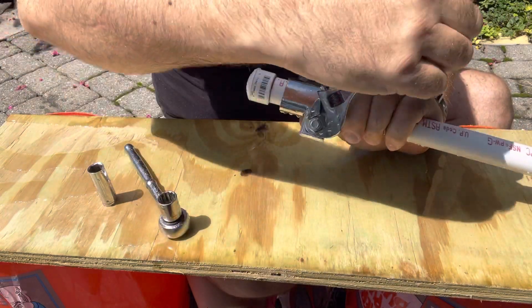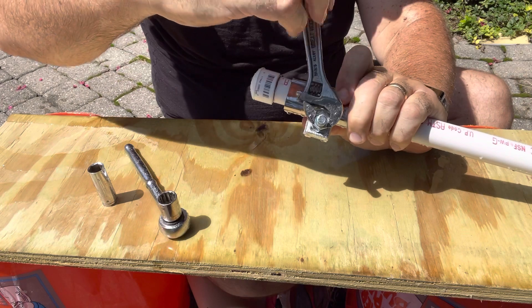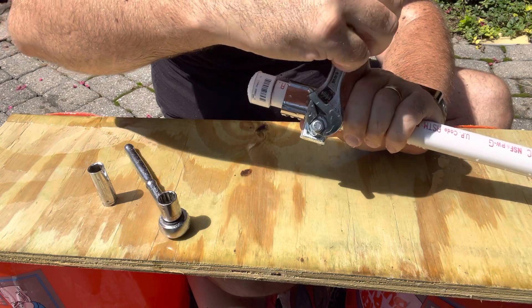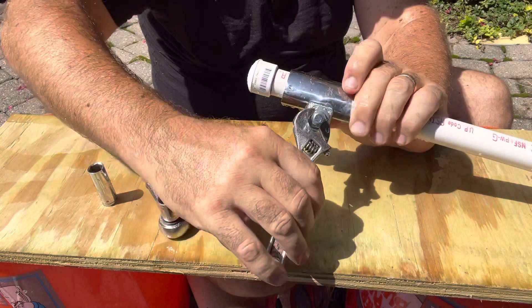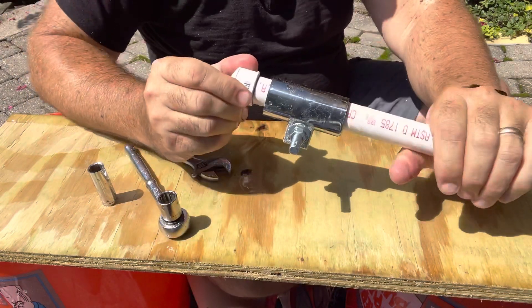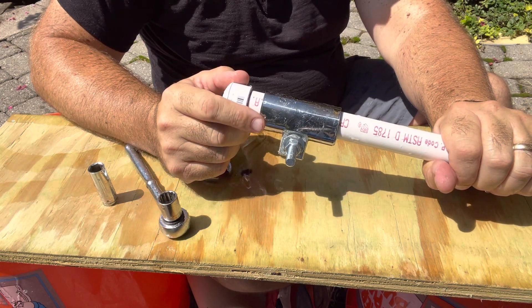The leak stopped. The manufacturer's recommendation says 25 foot-pounds torque, but when it feels tight and stops leaking, you're good. You don't want to push through the pipe. These same clamps work great for copper, steel, and PVC.